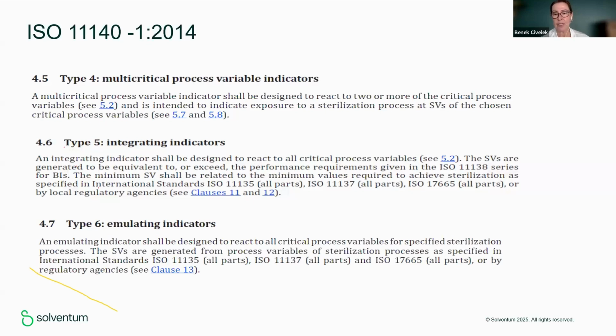Biological indicators, according to standards, are tested in three different time-temperature correlations: 121, 134, and 128. So they are taking the lethality curve around this time-temperature correlation. And in the same way, type 5 has three stated values and they are tested under these challenging conditions. Therefore, type 5 will give you more information about the quality of steam inside every pack.